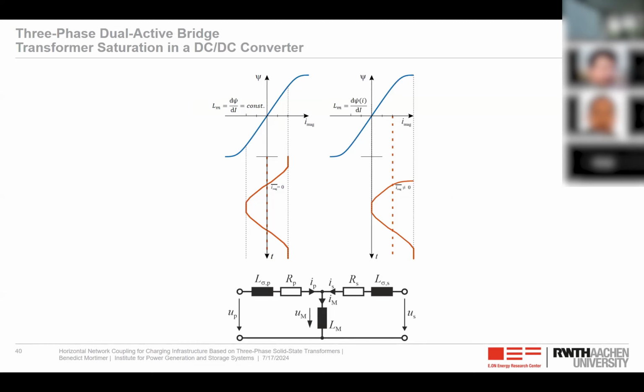So this typically happens if we have a DC offset on our magnetizing current, and due to this DC offset, we're operating in the nonlinear area of the flux linkage, and thus the main inductance is decreasing because the slope of the flux linkage is also different. And this then will typically cause some really high current spikes of the phase currents, because the magnetizing current and the phase current are somehow a superposition.